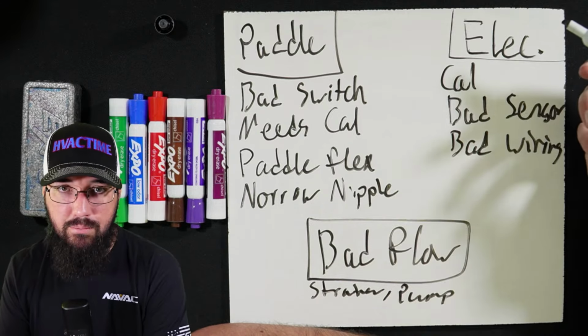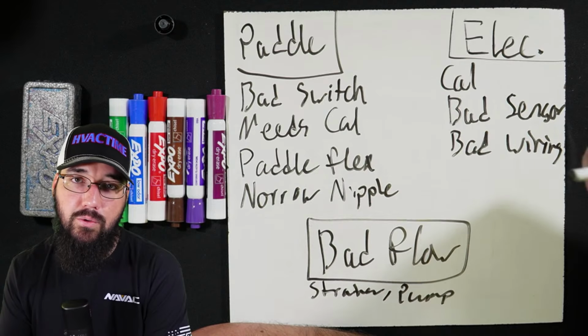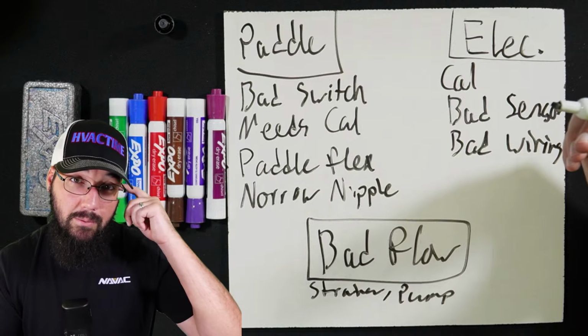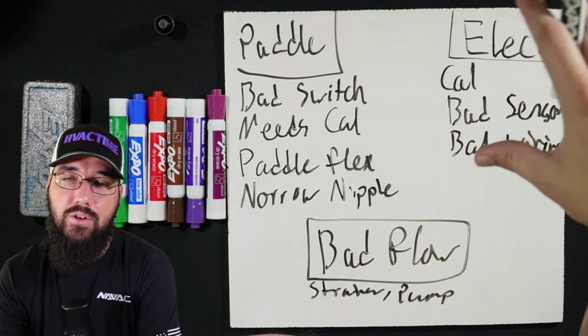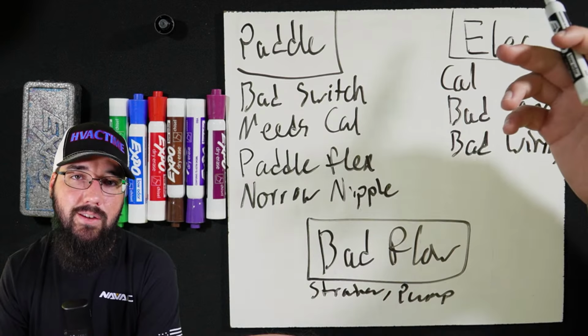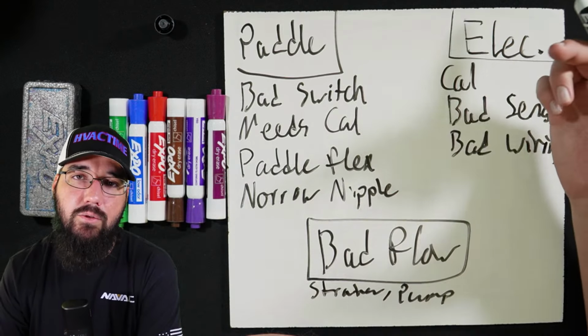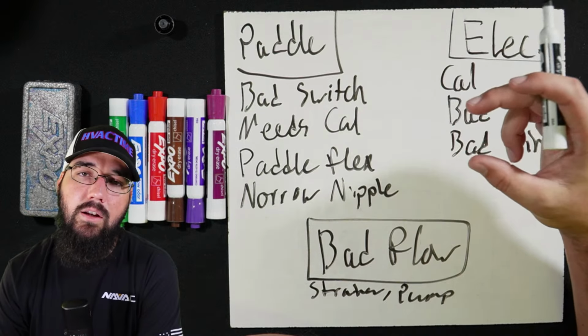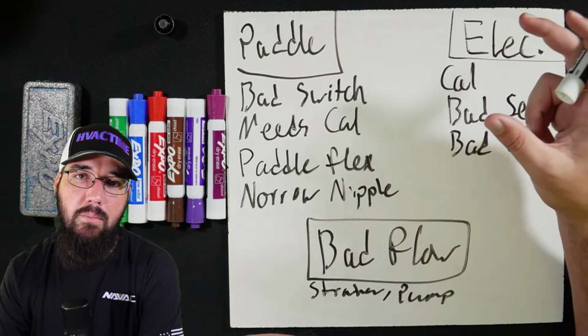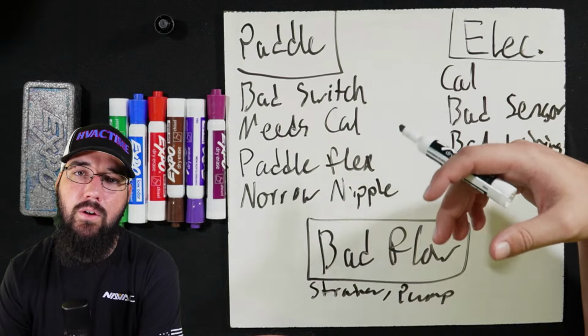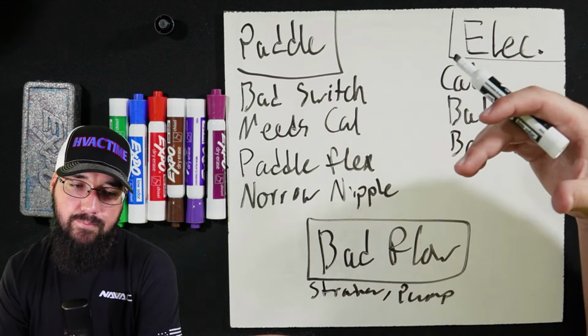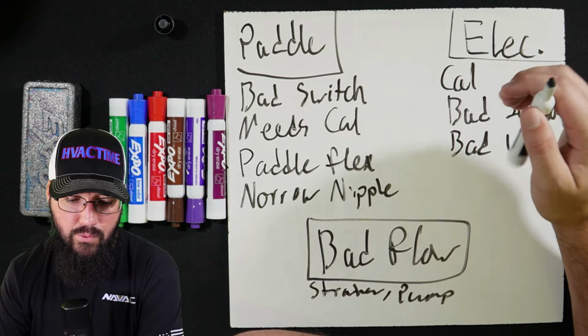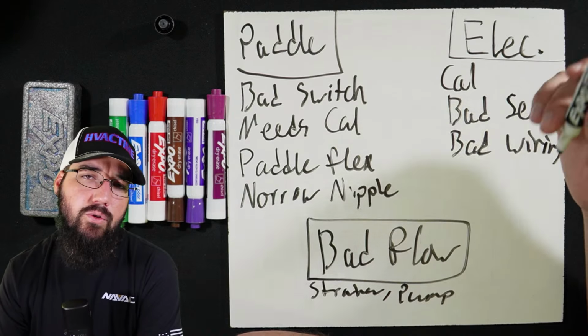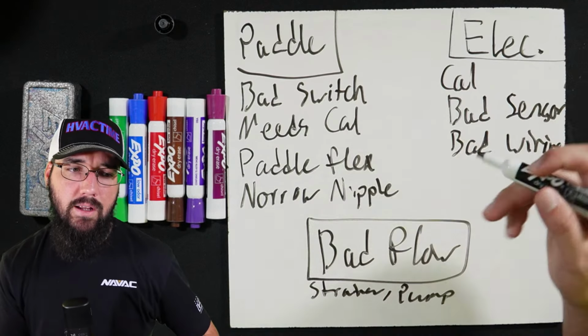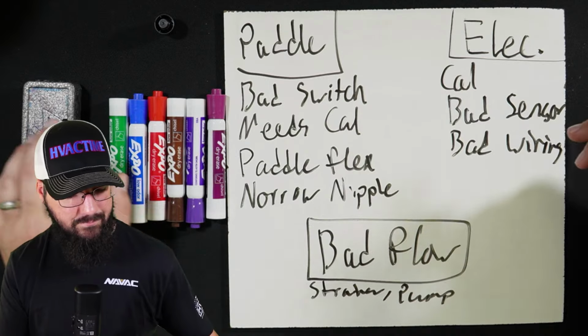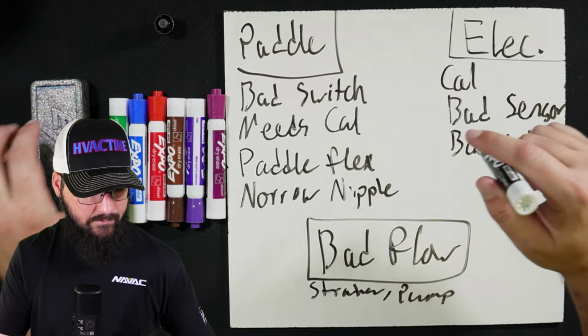Are the transducers able to actually read pressure properly? That could be an issue. So take the transducers out. Are the ports actually open? Are the transducers reading correctly? A lot of those DP sensors, you'll either have a reference chart or they'll have a little display on them where you can read the pressure that it sees. One of those options is typically true. So you can read the reference feedback from the transducer to the controller to see, okay, it's this VDC coming into the controller means X pressure from the transducer. Is that correct, if you compare that to a calibrated gauge? If it's not correct, then is it the transducer or is the port itself plugged up? You need to clean the port, and then the transducer will suddenly start working just fine. All right, that wraps up that one.